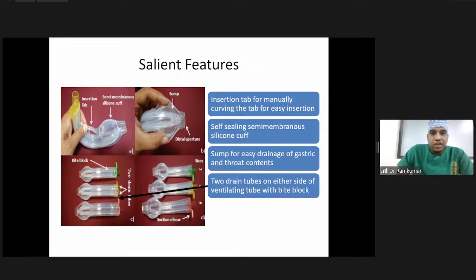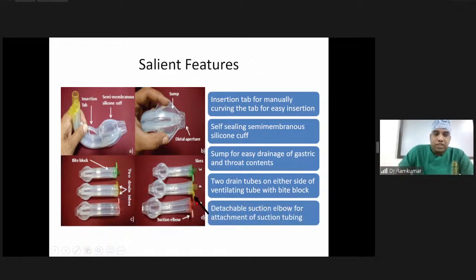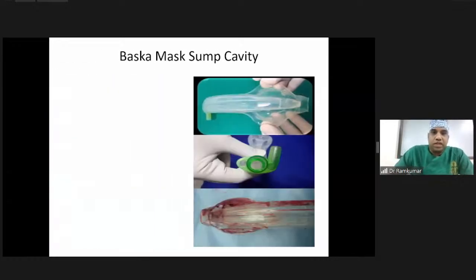Next is the suction elbow on the drain tubes, which are there on either side of the ventilating lumen. This is the ventilating lumen. You can see the ventilating lumen. On either side is a sump, and there's a suction elbow that can be attached to either side to attach to a direct wall mount suctioning. So you can have high negative pressure suctioning as well.